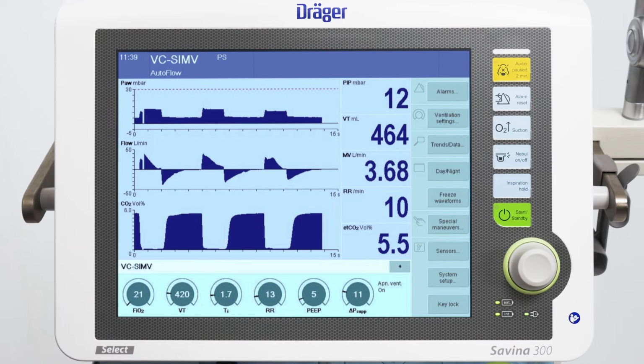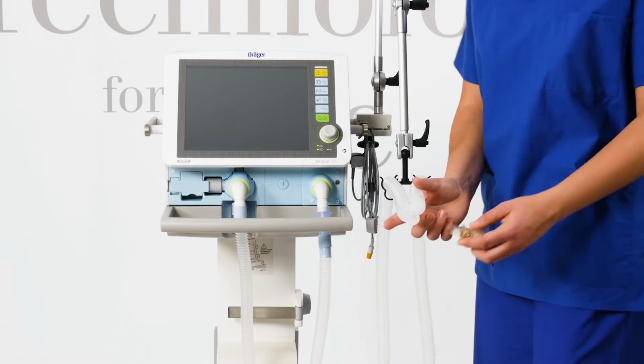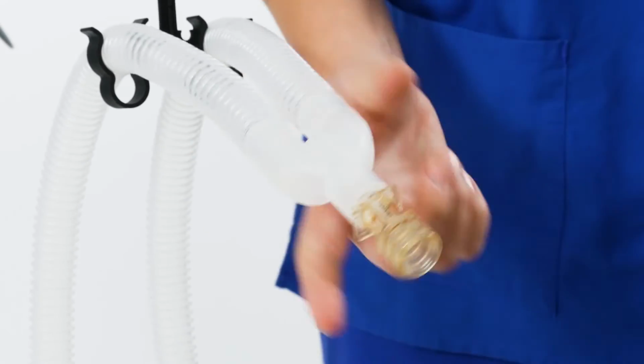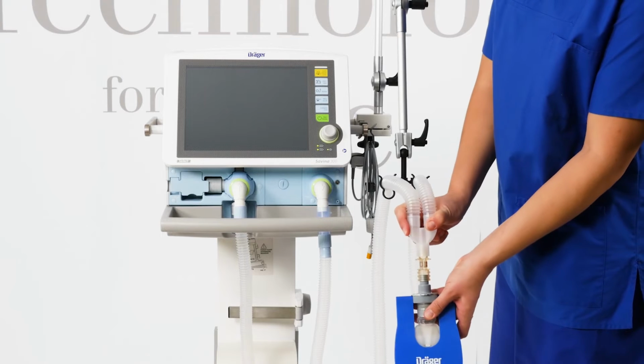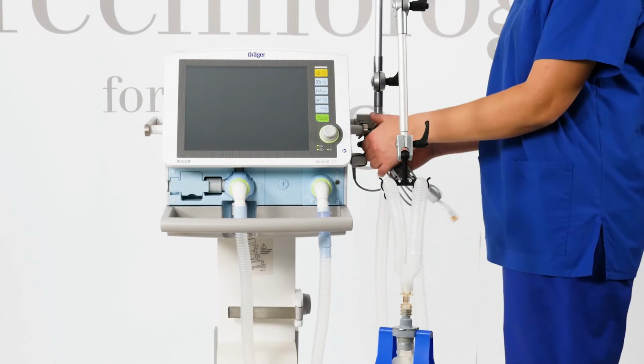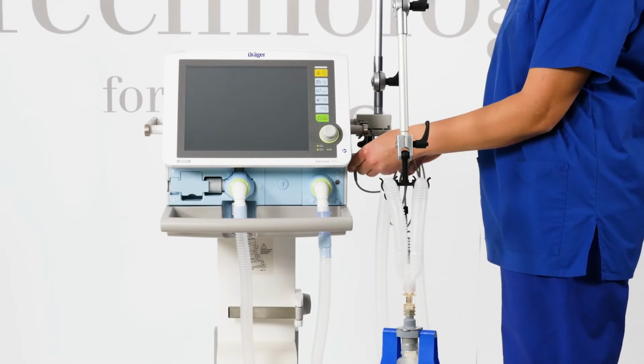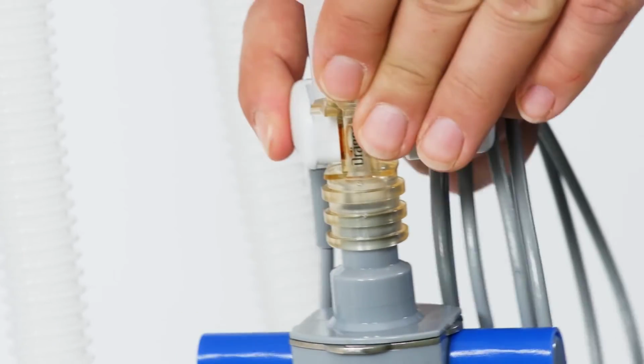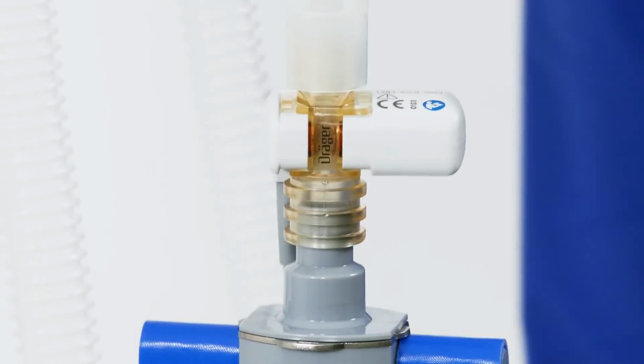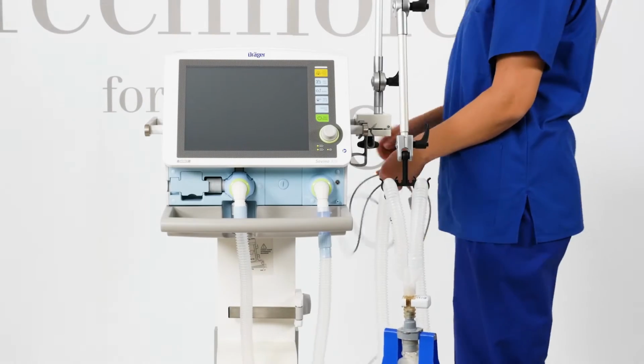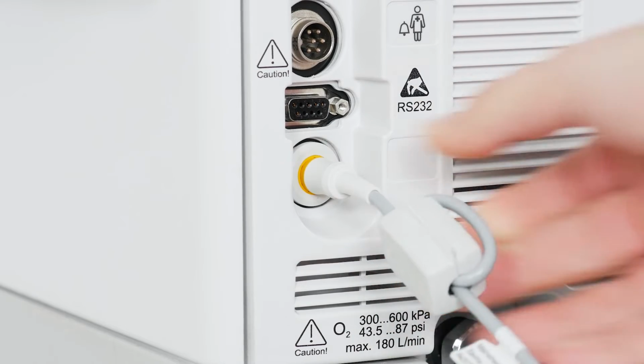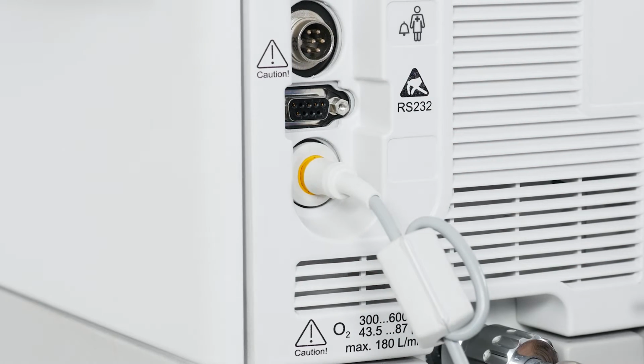The option CO2 offers the possibility of a CO2 mainstream measurement directly at the Y-piece and delivers measuring data in real time. They are shown as a graphic and as numerical values on the screen of the ventilator. Insert the cuvette into the patient connector of the Y-piece so that the cuvette windows are facing to the side. Afterwards, push the CO2 sensor onto the cuvette. Plug the CO2 sensor connector into the socket on the rear of Savina 300 Select.